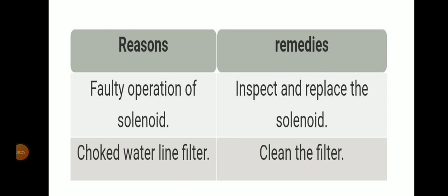The reason is faulty operation of solenoid. That means inspect and replace the solenoid. Choked water line filter means we have to clean the filter.